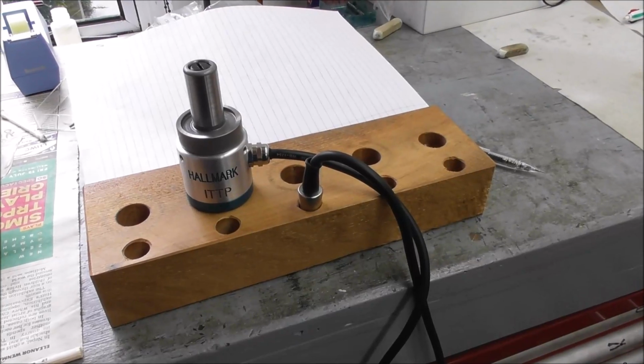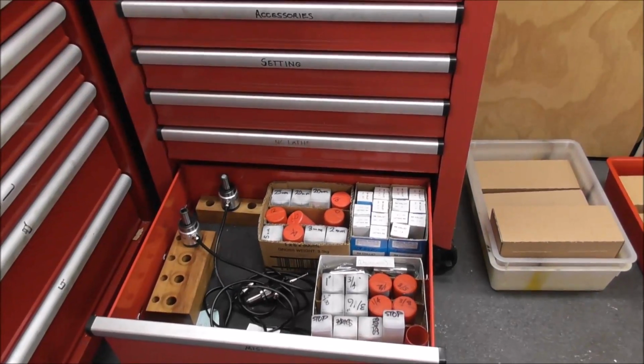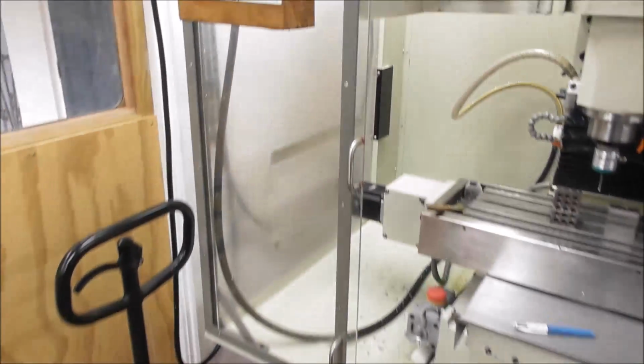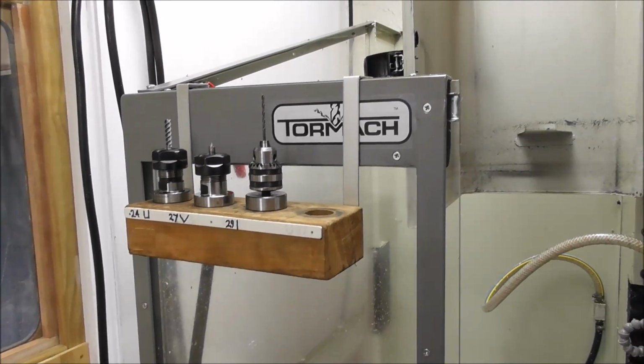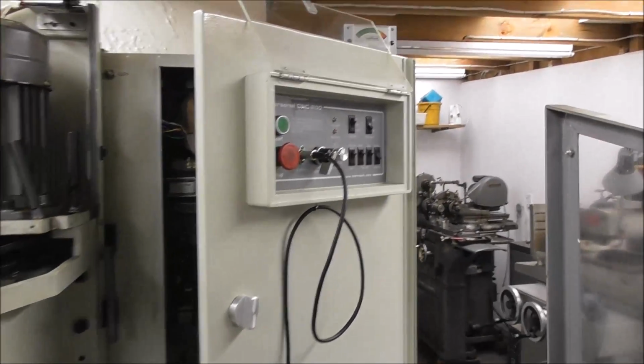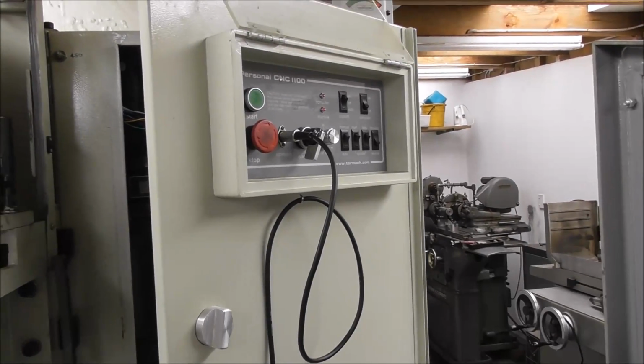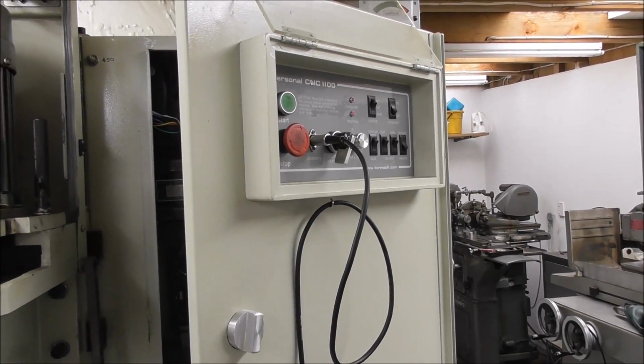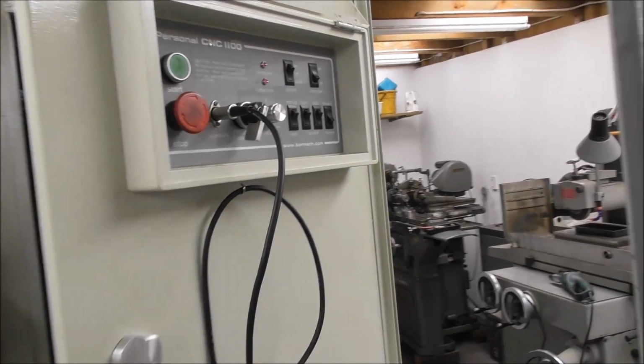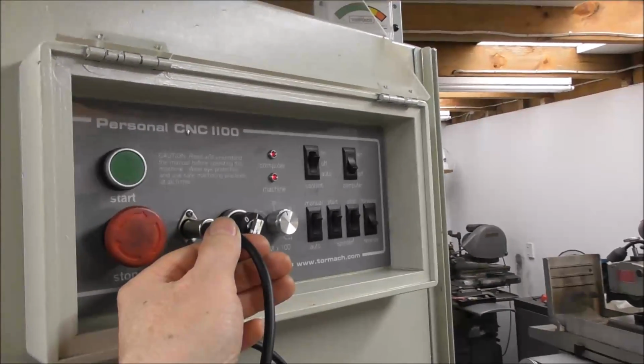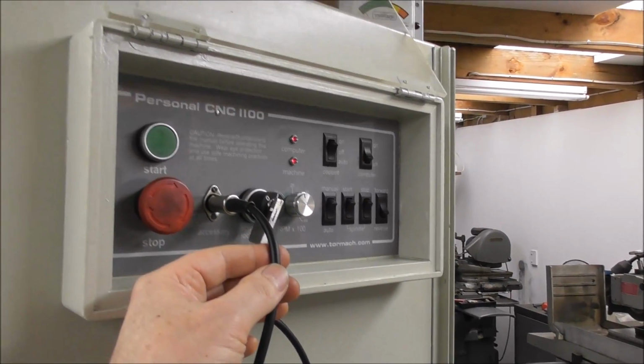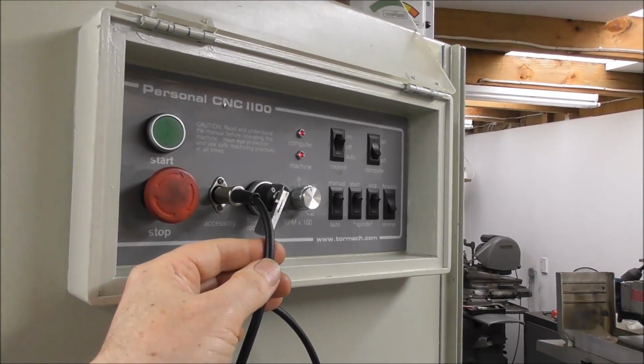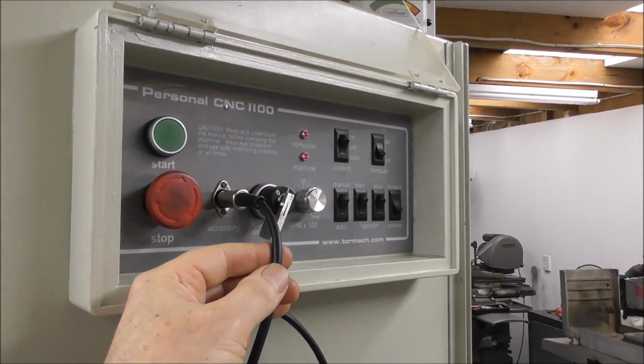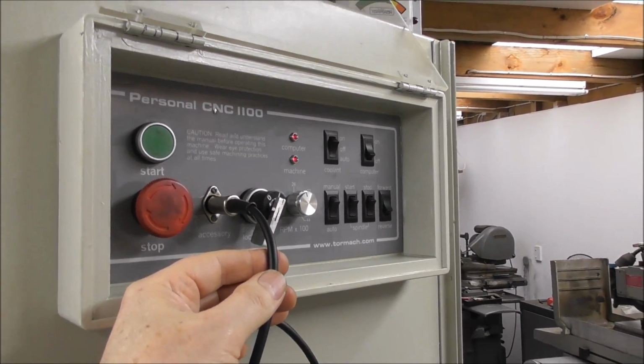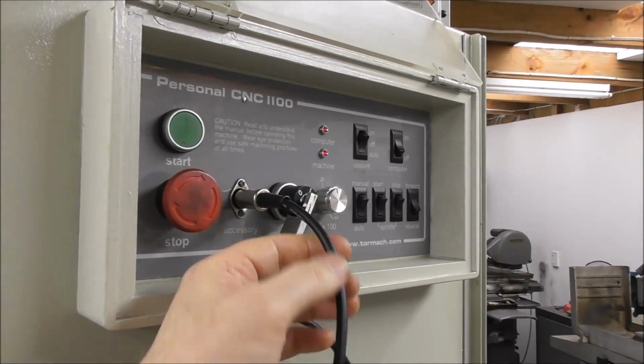So your probe is stored in a little block. It might be off the machine, it might be in your mechanic's cabinet, it might be clipped onto the front of your enclosure, or it might be screwed up on the side of the cabinet door. Just make sure it's in an area that doesn't get sprayed with chips and coolant. Now I know some users leave their probe plugged in, and if you speak with Tormach about it, they will say that's not best practice. I know some people are getting away with it, but it's not best practice, and let me try and explain why.